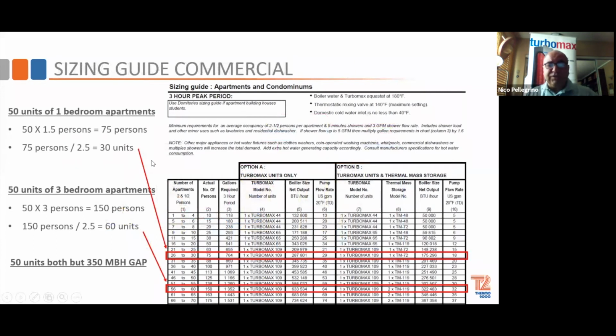So we do have sizing charts available, both for 180-degree boiler water and also for 160-degree boiler water. The important thing when you're looking at the sizing charts is to make sure you know what you're sizing. The peak period is very important, usually the demographics of the building, and also how many people are in the building. We base it on 2.5 people, but if you have less, you can go to the 75-person column, and that's what your Turbomax is.